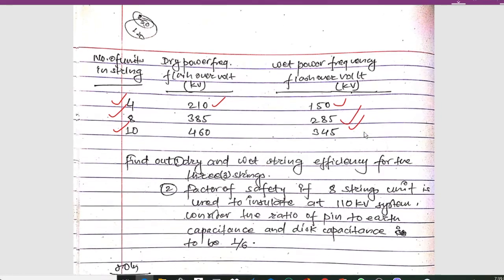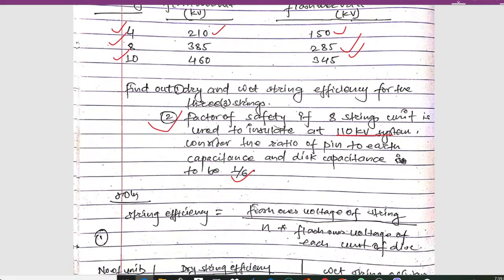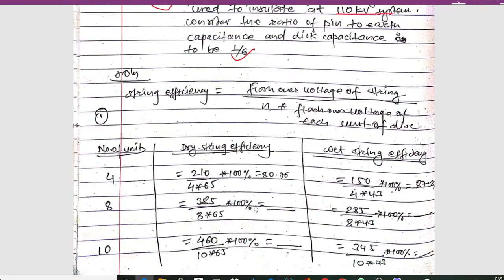We have to calculate the dry and wet string efficiency for 3 strings. In the second part, we have to calculate the factor of safety if an 8-string unit is used to insulate a 110 kV system, considering the ratio of pin-to-earth capacitance to disk capacitance to be 1/6. The string efficiency formula is: string efficiency = flashover voltage of string divided by (n × flashover voltage of each disk).